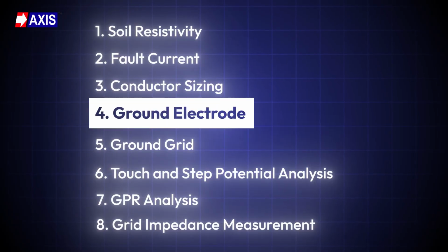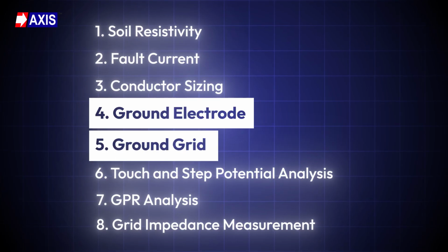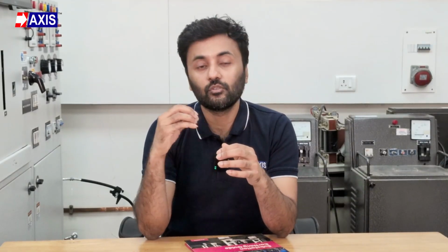With the conductor size, we move to steps 4 and 5 of the design process: selection of the ground electrode and the ground grid. The conductors are embedded into the earth as ground electrodes, which collect and dissipate fault current into the soil.